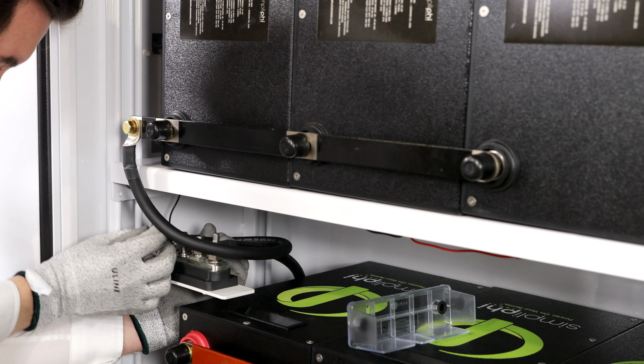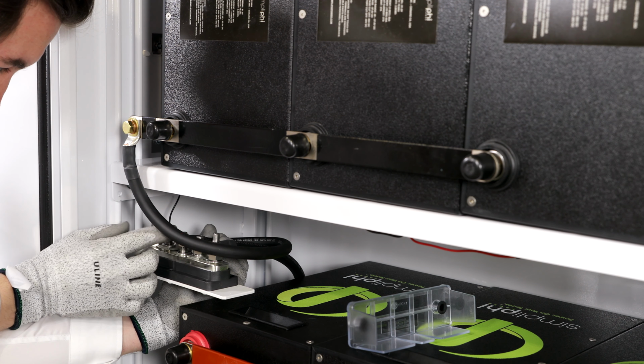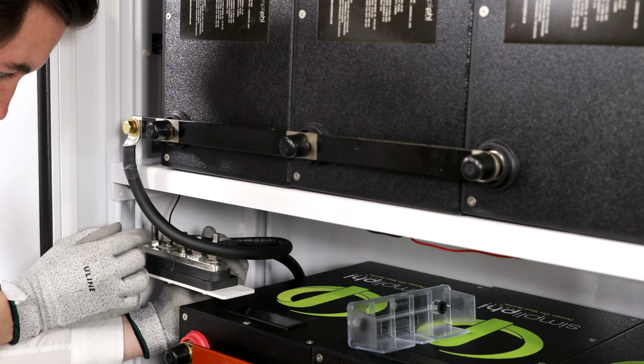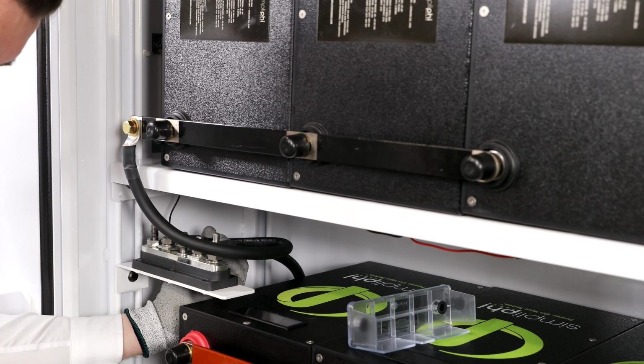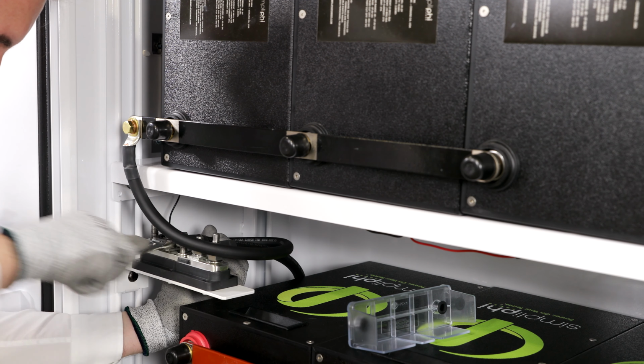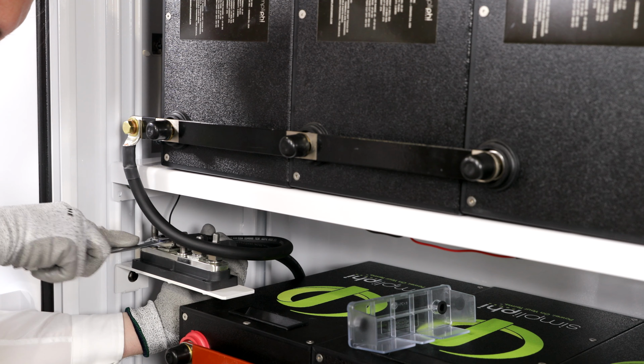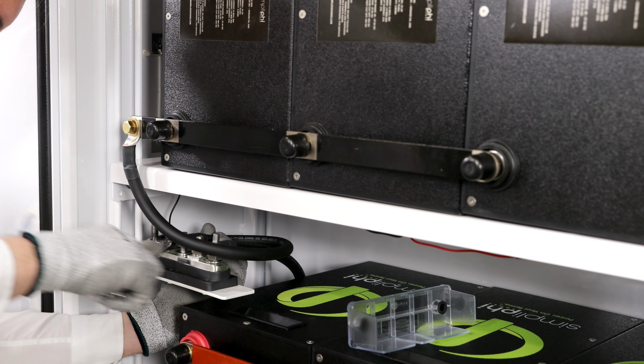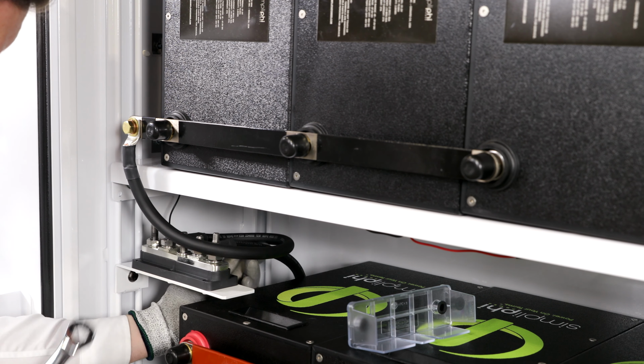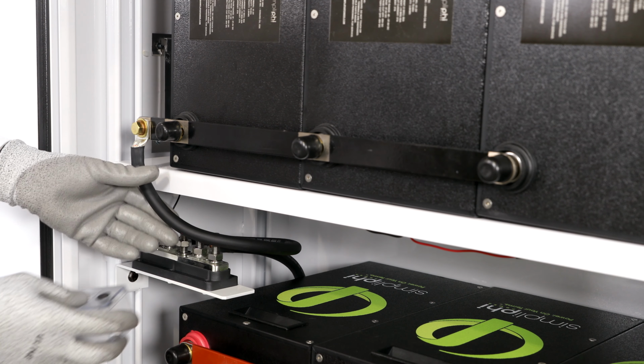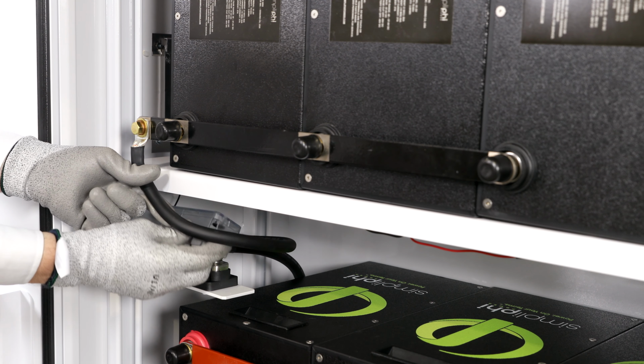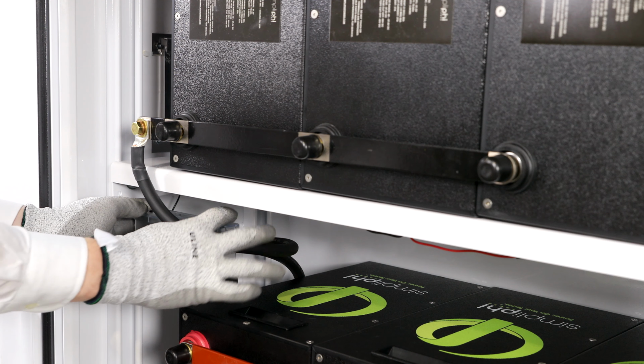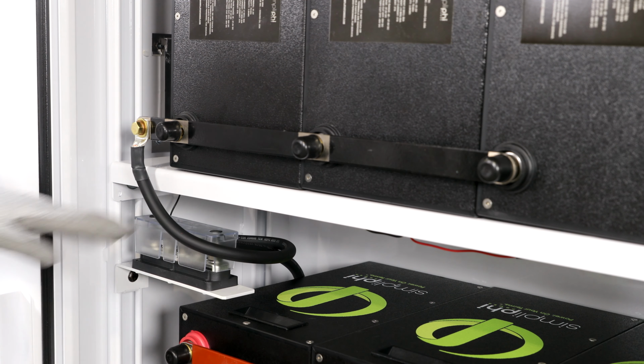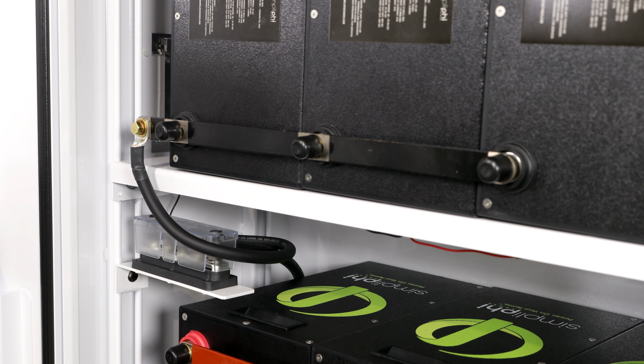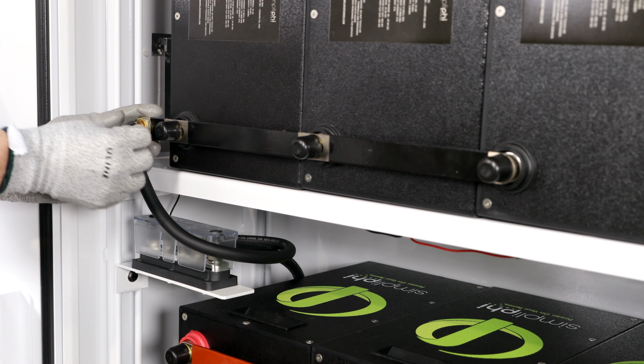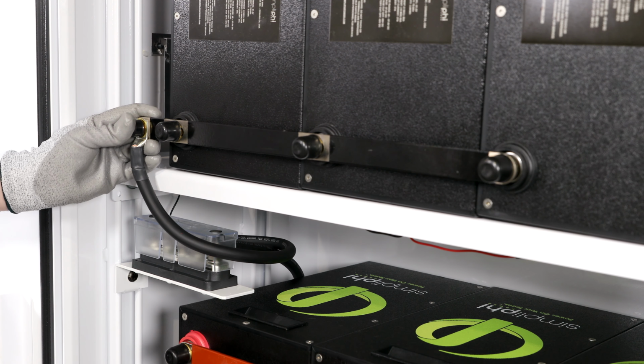Attach the cable's lug to the 5-point terminal block, followed by the lock washer and nut that were removed earlier. Firmly tighten the nut to secure the cabling lug to the 5-point terminal block. Now, both negative bus bars should be secured to the 5-point terminal block. Replace the plastic covering over the 5-point terminal block that was removed earlier. After securing the lug to the bus bar, place the black bolt cover over the brass hex bolt.